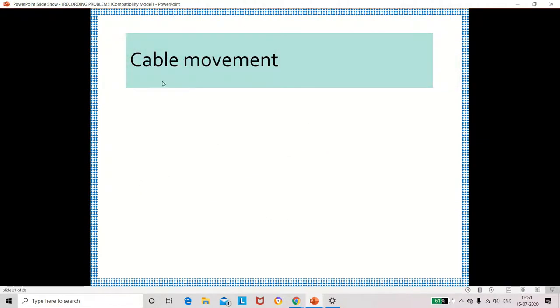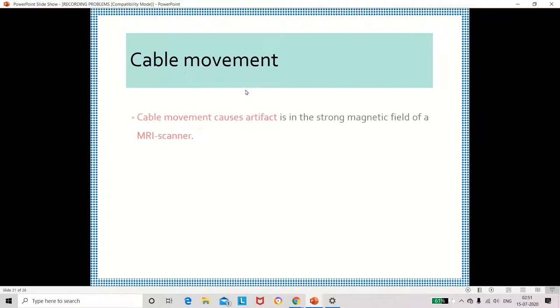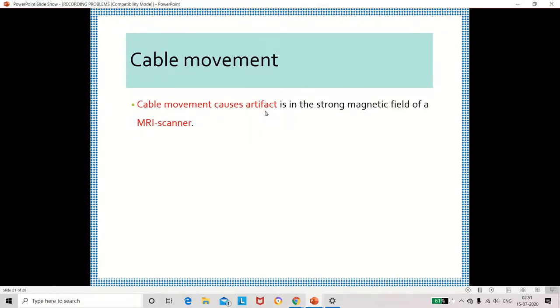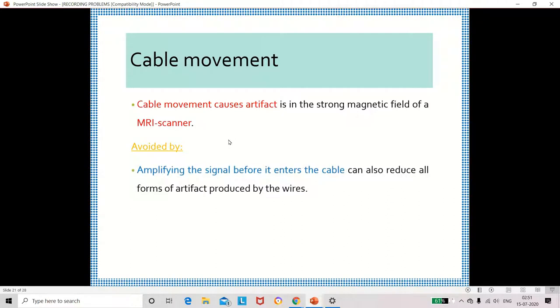The next noise may be created due to cable movement. While measuring the potential we use a cable, and if the cable is moving it may create some artifact. To avoid this, we should amplify the signal immediately after measuring the bioelectric signal, and then pass it through the cable to the display device.